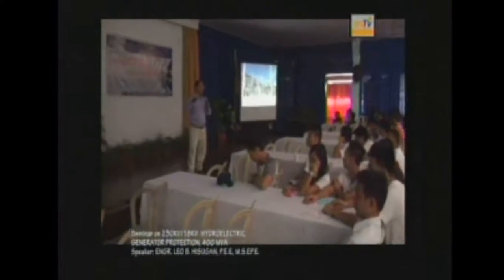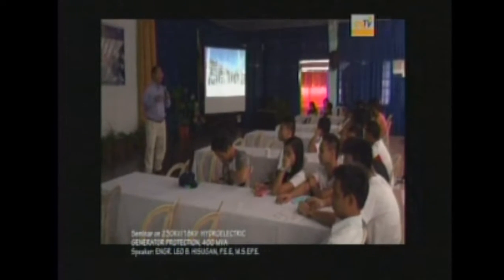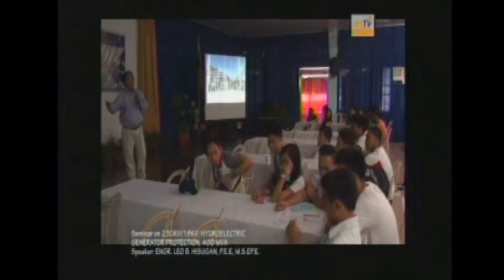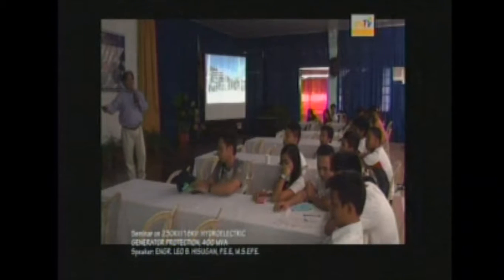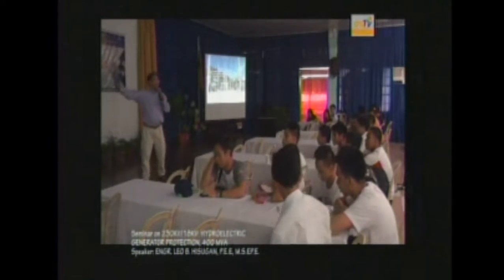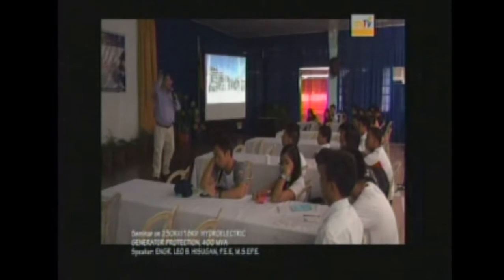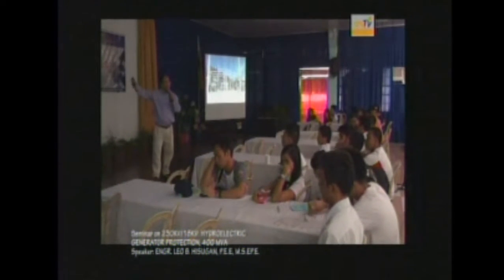This is a CCVT, and this CCVT is called. What is the meaning of CCVT? Any takers? This is one of your instrument transformers that provides power to your relays and metering units that became usable for metering and protection. Any takers? CCVT. Not yet? Okay, so your CCVT is your coupling capacitor voltage transformer, right? Or your potential transformer.